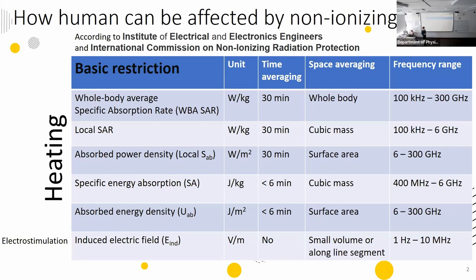For frequencies higher than 6 GHz, the penetration depth is low, so you don't need to calculate SAR in the volume of your body. Instead, you need to calculate the absorbed power density at the surface of your body, and you average it over a surface area of 4 cm² or 1 cm², depending on the standard.